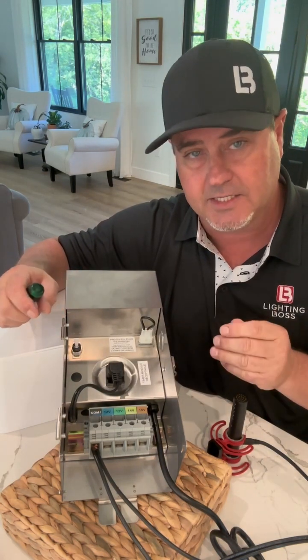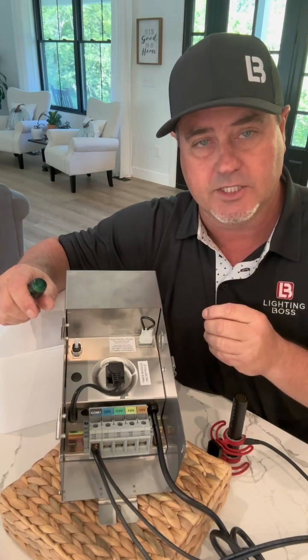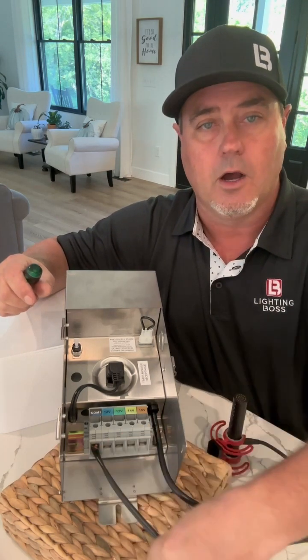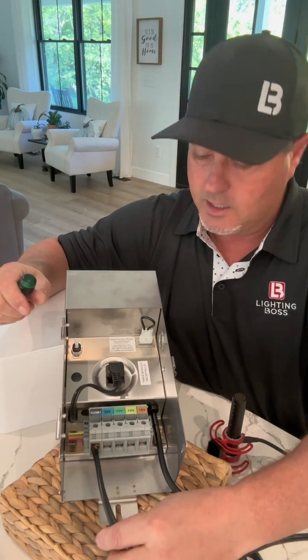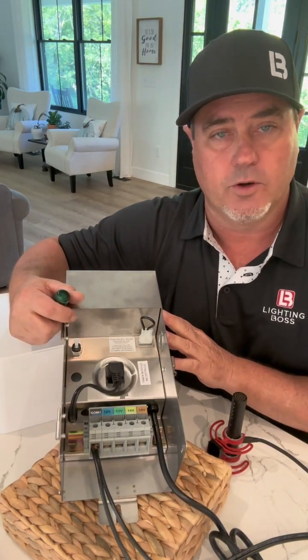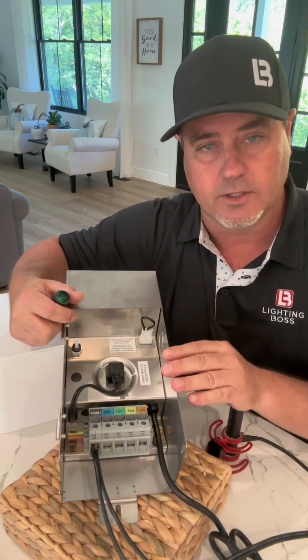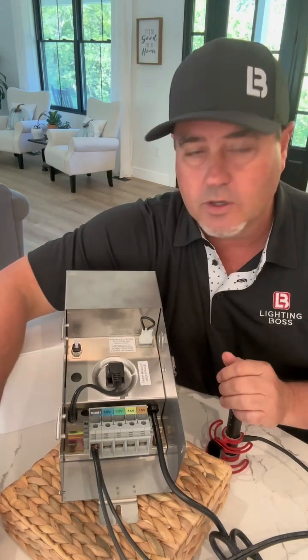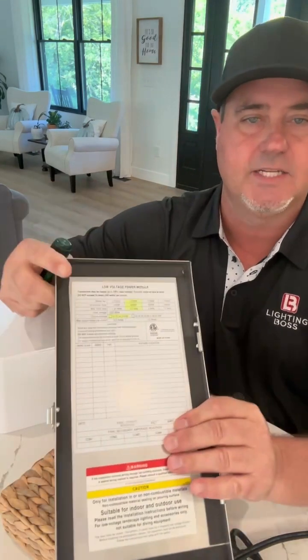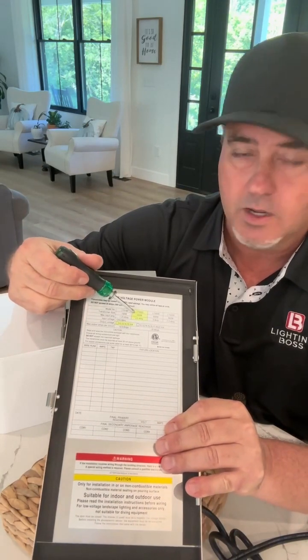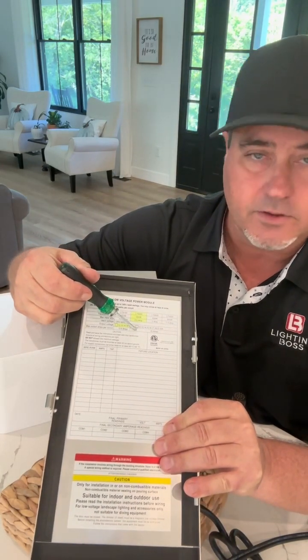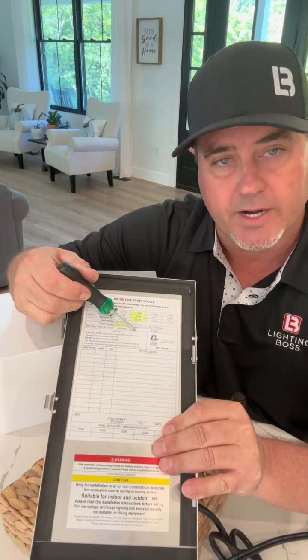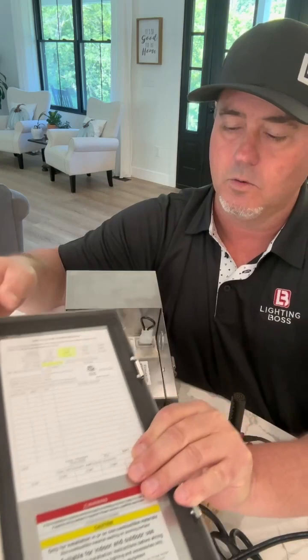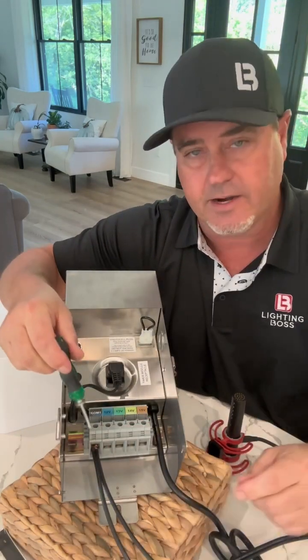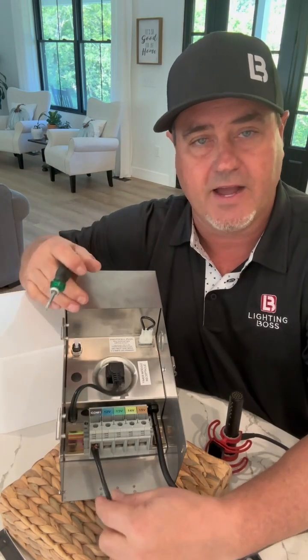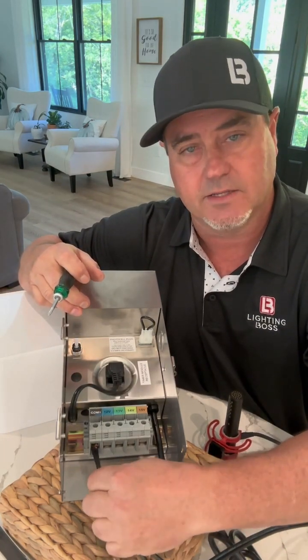Now, what it does is it protects the amperage that comes into the transformer on the secondary, or low voltage side. So when you're testing your low voltage lines after you have a load on the transformer, you can look on your transformer. Most of them are very similar. A lot of them are going to tell you what size transformer you have, and then they'll have a little chart that lets you know what the amperage reading needs to be or less. For this particular transformer, on the secondary side, they tell me that I need to have 25 amps or less when I go to test this particular transformer.